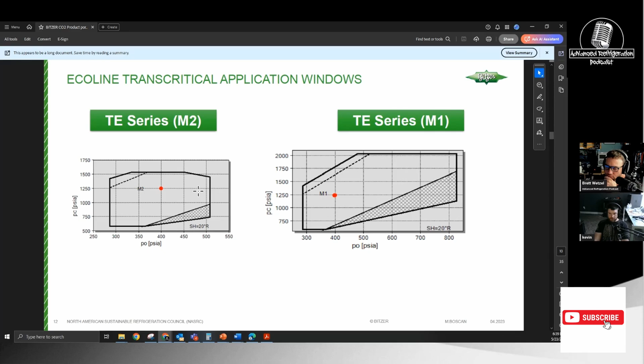Only if it has the transducers. Oh, I see what you're saying. So if something were to go awry with the program and everything just freezes, that thing is still going to have control. If it were to go outside its envelope, where this one would have a suction of X, it would basically say, nope, not today, and just shut down. That can cause some random lockout issues, but like the head pressure one, I totally agree, it keeps it from blowing a relief again. It's one more layer of protection.